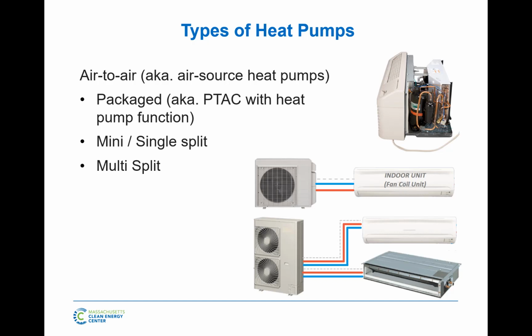Sometimes people will do a hot water as a backup, especially a retrofit. I already have radiators that do hot water. My boiler is decent, so let's just leave those there, and we'll put a VRF or air source heat pump in, and I'll only use those if I need to, or on certain days when it's really cold and cost-wise it might make sense. We'll talk about that a little bit later.